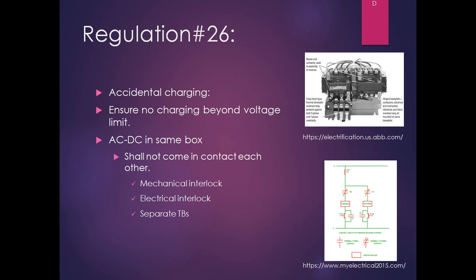Accidental charging. So there should be protection against accidental charging. It has to be ensured that the charging is within the specified voltage limit only. If AC and DC are used in the same box, they shall not come in contact with each other. See, here is an example for achieving this purpose. In industry, it is very common practice to provide the normal supply from the AC and the emergency backup standby supply from the DC. So those things are taken by using contactors. So contactors can be provided with interlock.